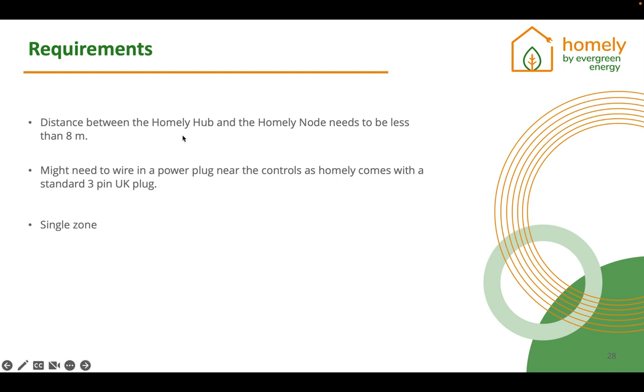but that support will only be coming in the new year. If you do have an issue in terms of the distance, the Homely node usually needs to be placed in the living room, so it is usually the Homely hub that you'll need to move. You'll need to place the Homely hub closer to where the node is going to be. You can do that by extending the Modbus cable. The Modbus cable can be extended up to 30 meters, and that would allow you to place the Homely hub close to the node so that there are no connectivity issues between the hub and the temperature sensor.